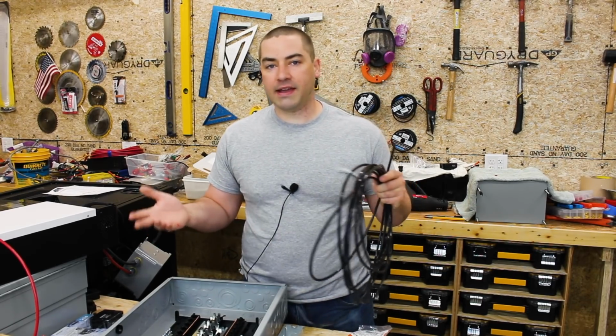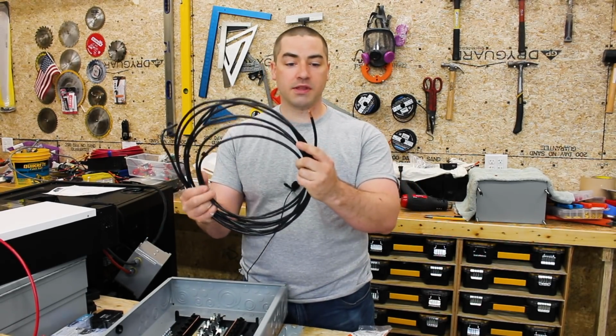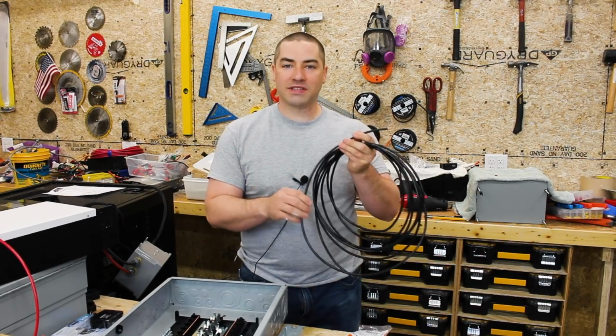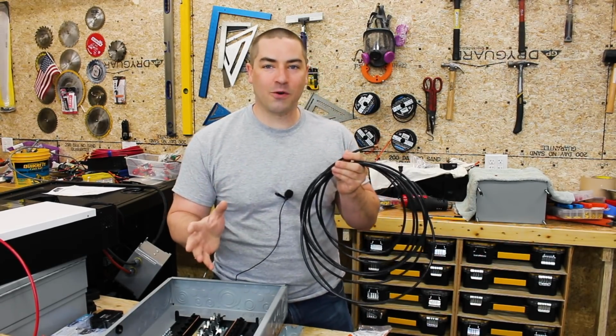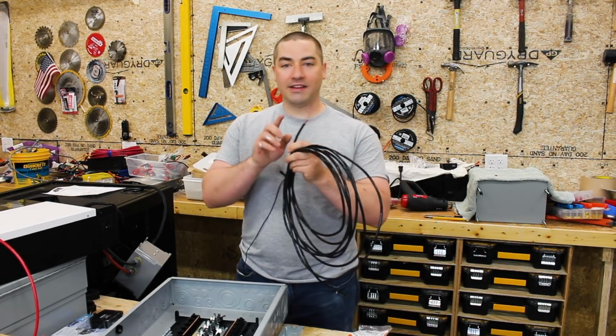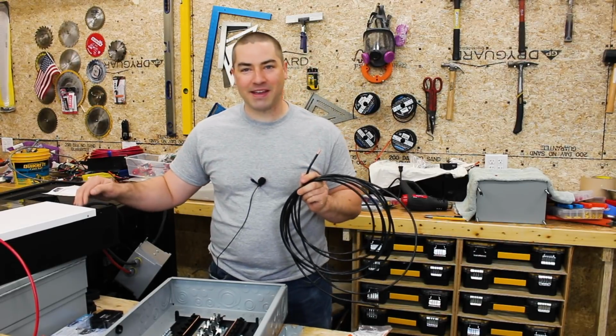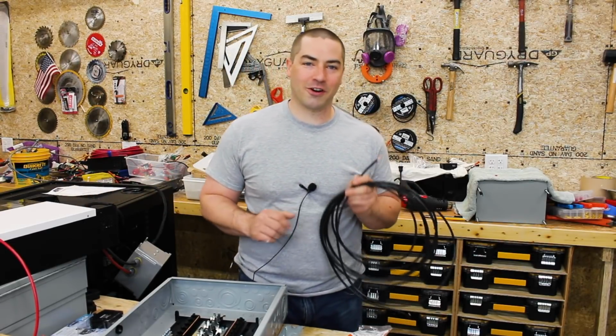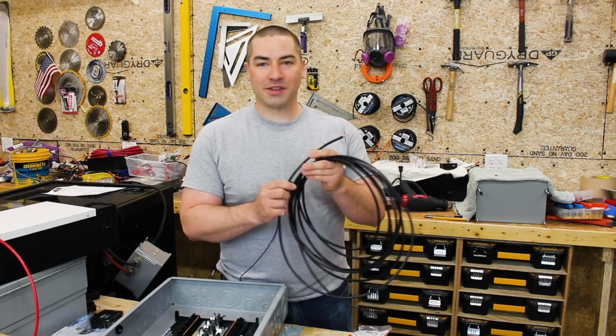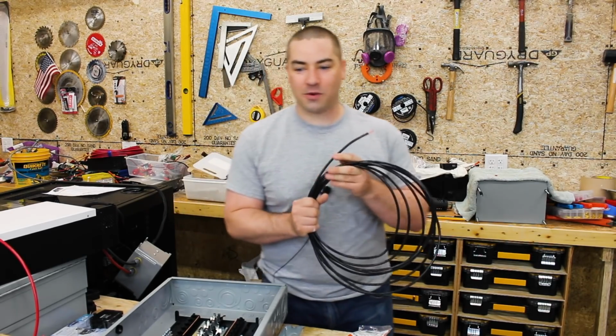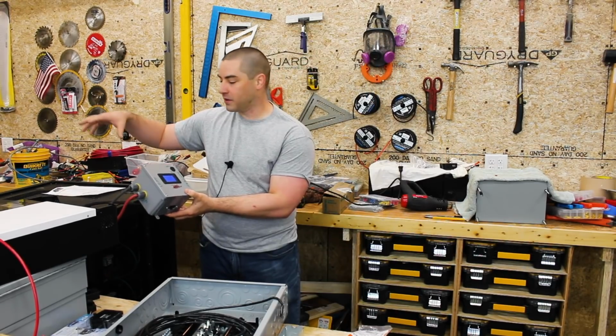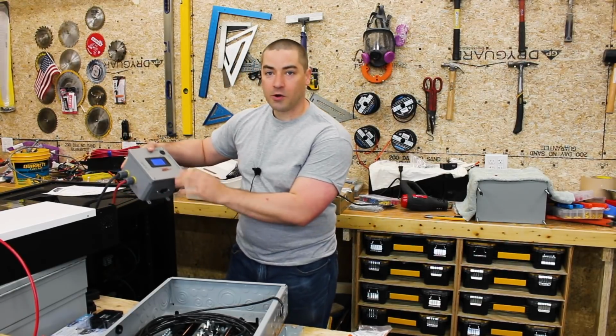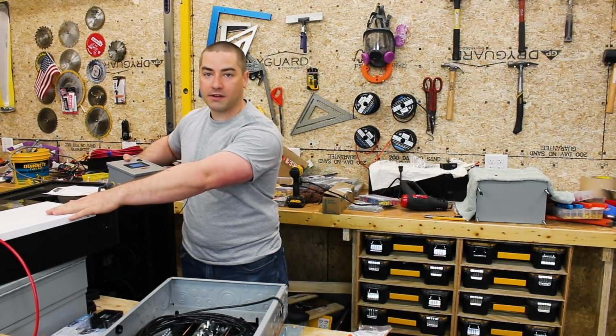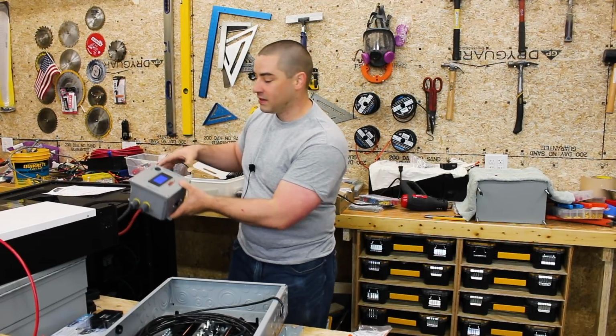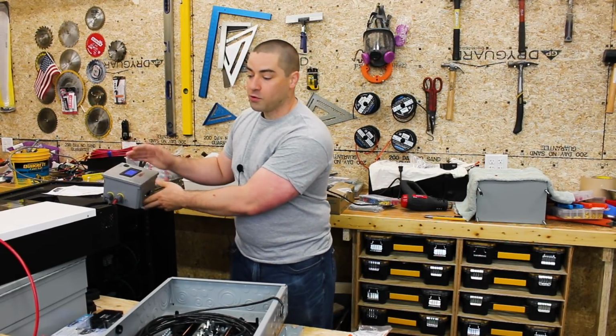Now, I don't have any 8 gauge wire on hand, so we're going to be using some of this 6 gauge wire. So this 6 gauge wire is a little bit overkill, but that's okay. I did check and it just barely makes it into the terminals on the inverter. So it will fit, but I don't think you could squeeze any more than a 6 gauge wire in there. It's a tight fit. I also hooked up the battery with my watt meter over here connected to the Growatt inverter. That way we're going to see how many watts are moving in.